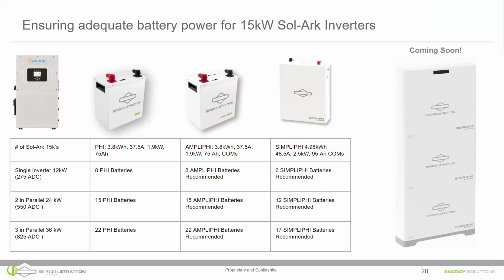And can we have less than what we show here on the screen? Yes and no. If you're using the non-communicating batteries, we do require a minimum number. You can program the inverter to draw less power than the maximum. So for somebody who wants to start off with a Sol-Ark 15k inverter but with a smaller battery system, you can program that Sol-Ark so that its output capacity is less than the 12 kilowatts.